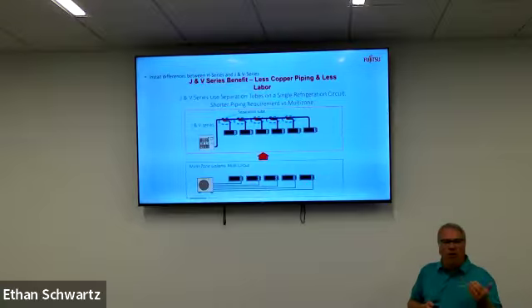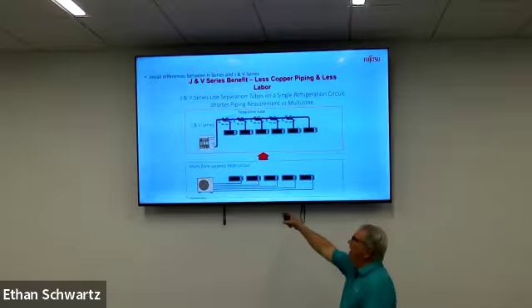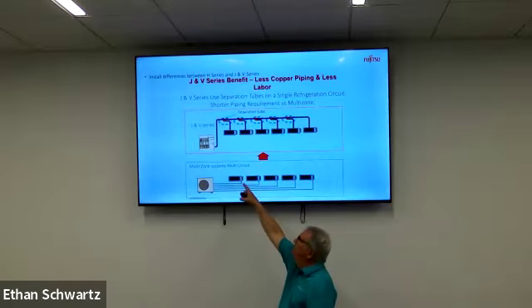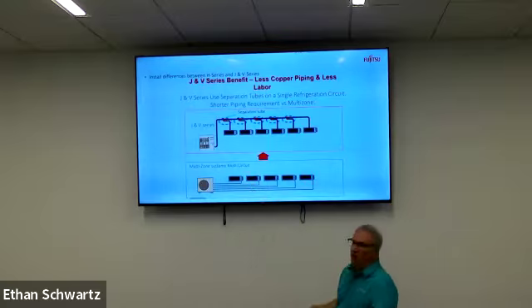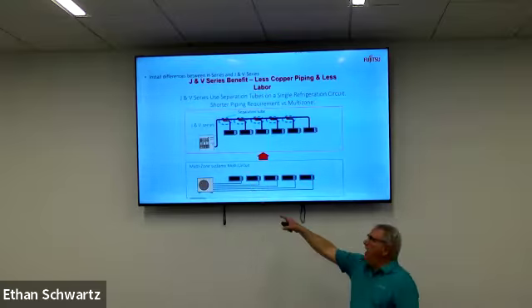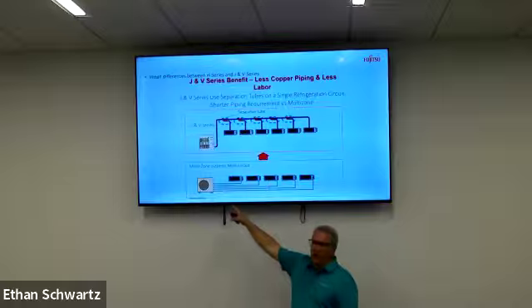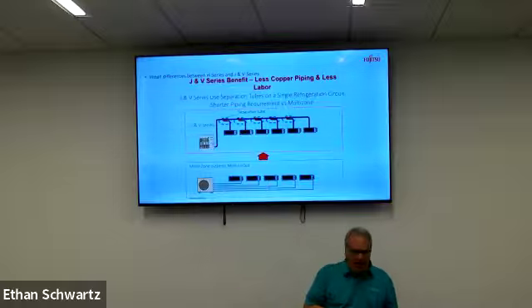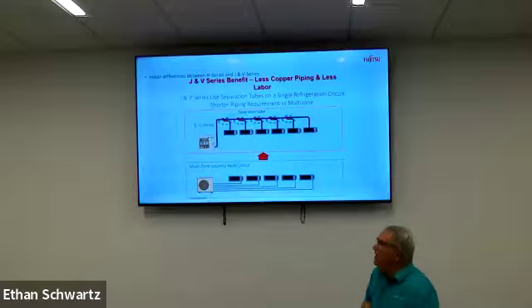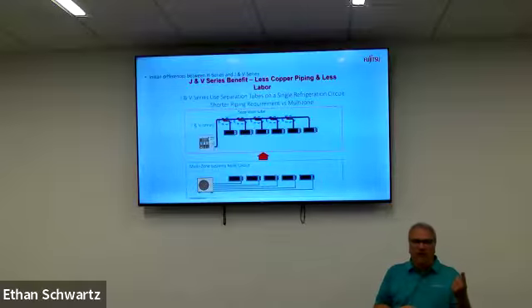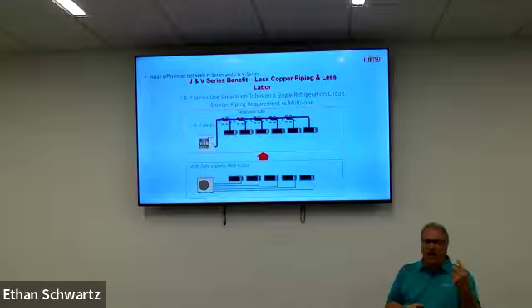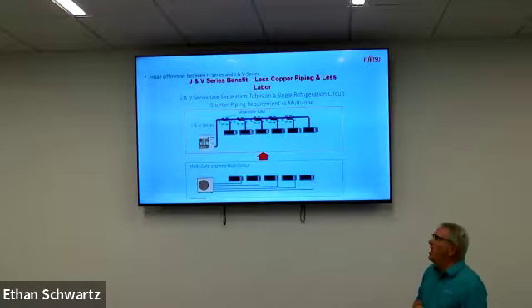If you're doing 1-to-1, say you're going to have a 2-ton system or a 3-ton system, and you're going to go to one air handling unit, one of our H series going to one air handling unit. There, pipe length limitations come into play, but also electric heat. I'm going to show you that in a slide here.